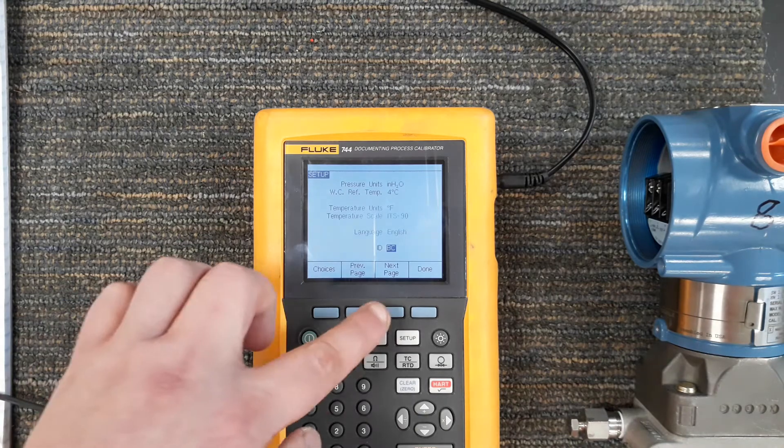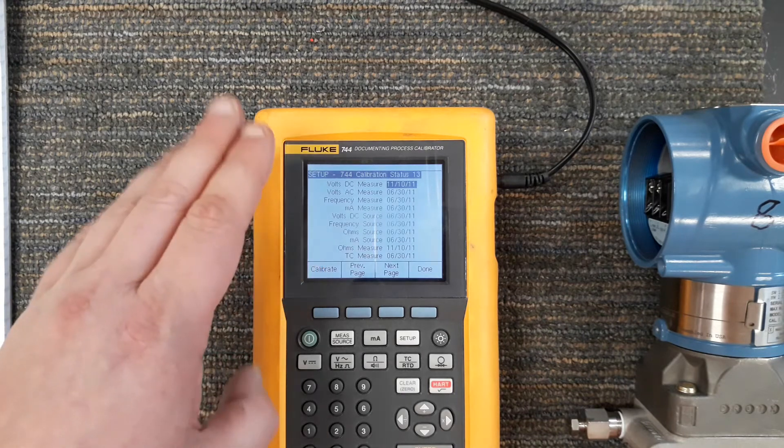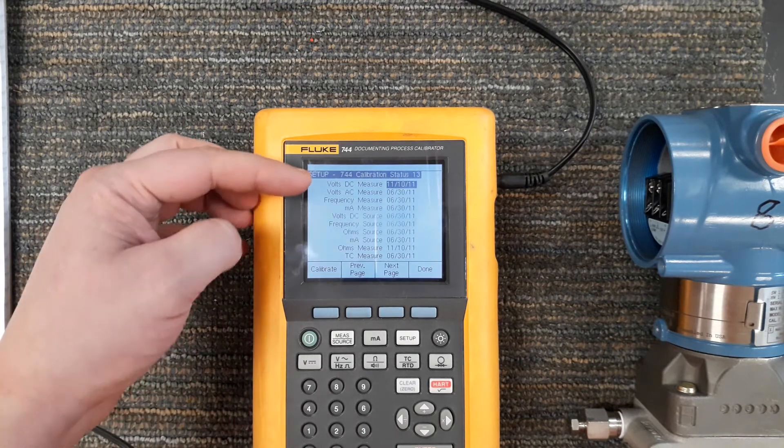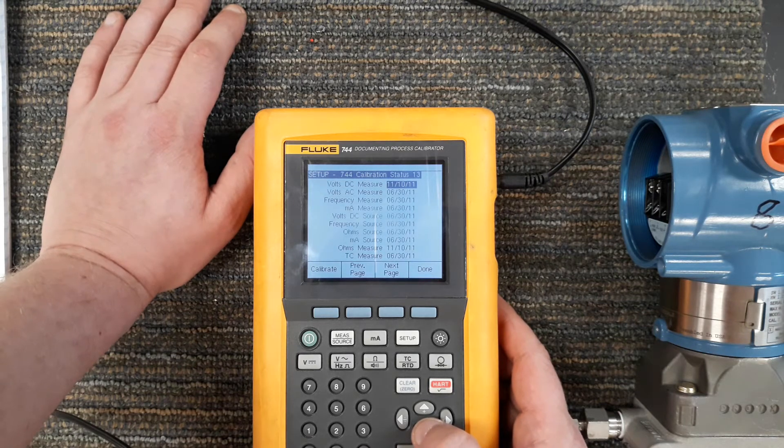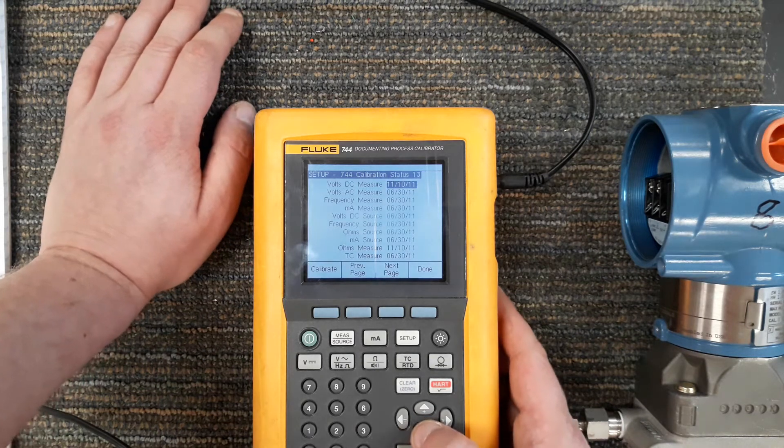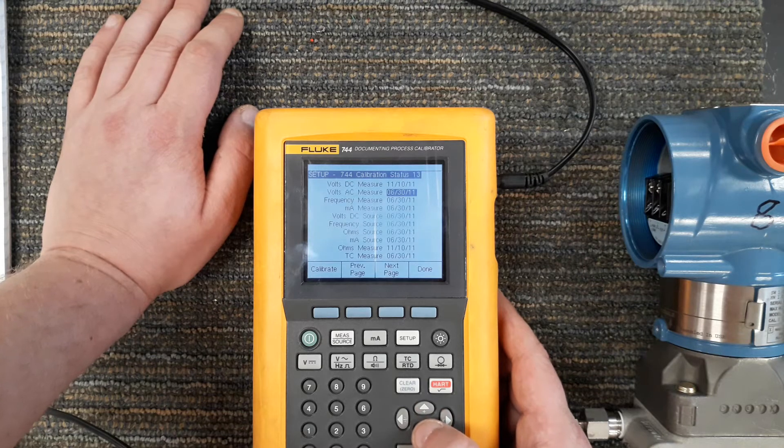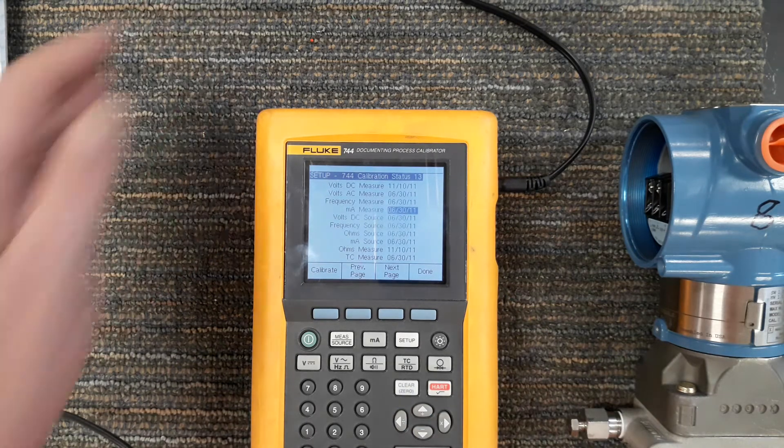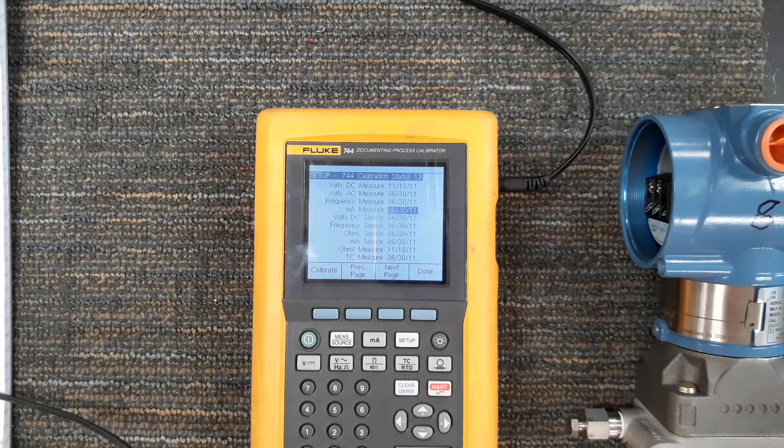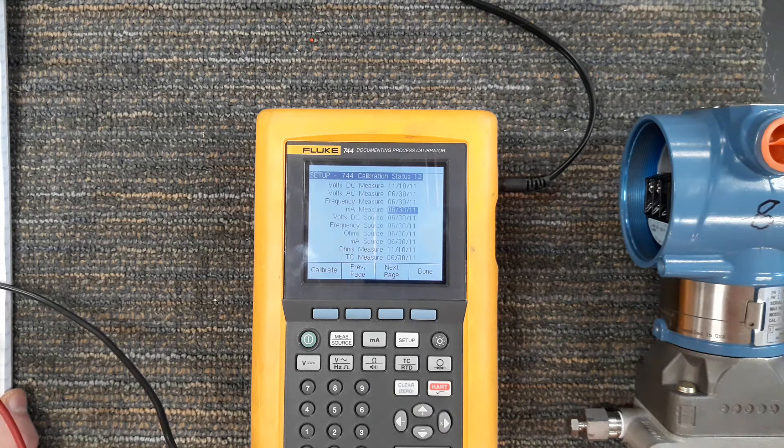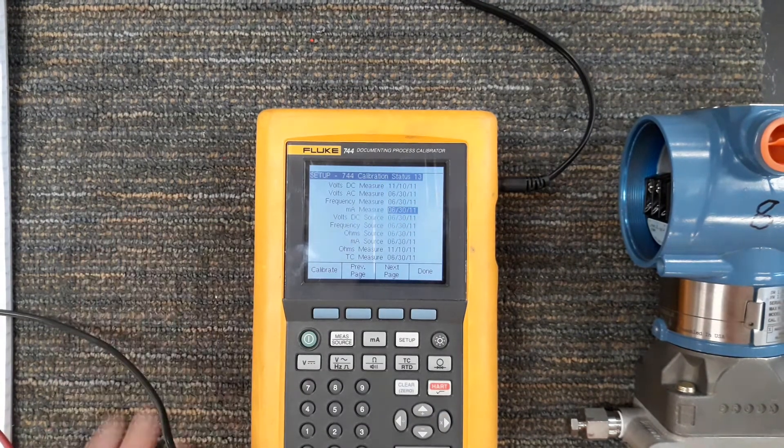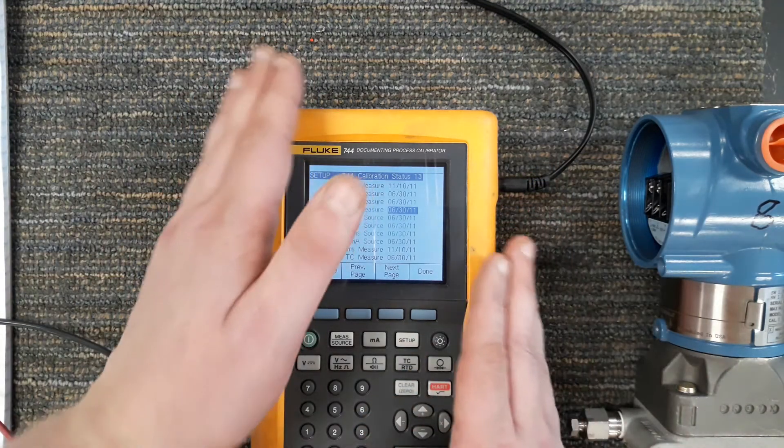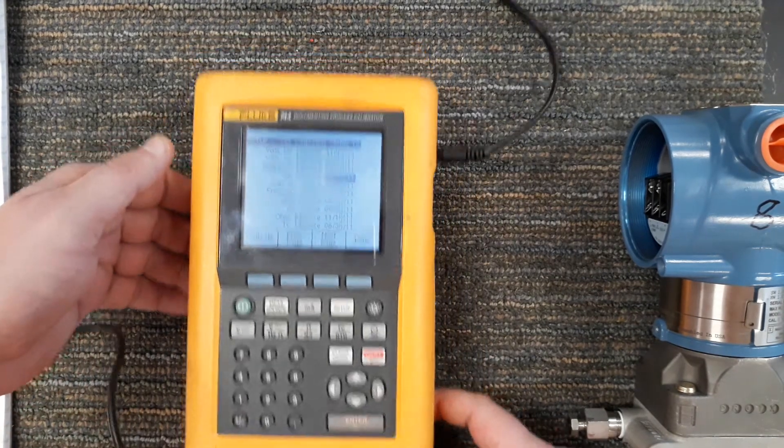Next page, this screen is going to tell you when last this meter had any calibration done to it and specifically what type of calibration. So here you can see that the volts DC measurement capability of this was calibrated in November 10th of 2011 but the AC voltage was calibrated in June 30th of 2011. This gives you very good detail of when the last time it was calibrated which is very important. Maintaining calibration on your equipment is important because everything we do in the field is gonna be based upon the accuracy of the calibration of the test equipment we use to calibrate those items. So ensuring that this is calibrated frequently is going to increase the accuracy of our devices.